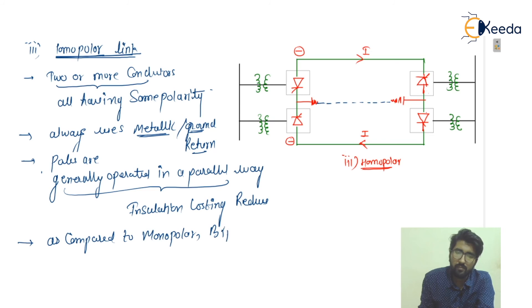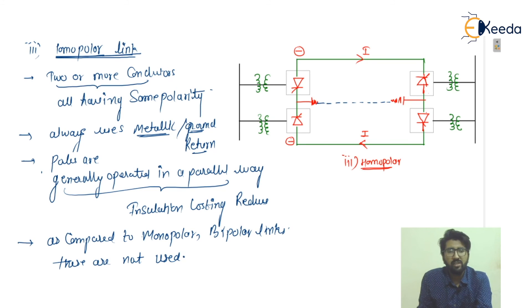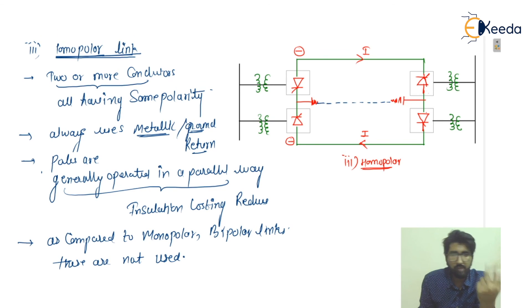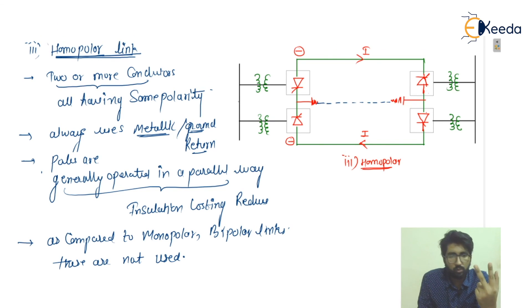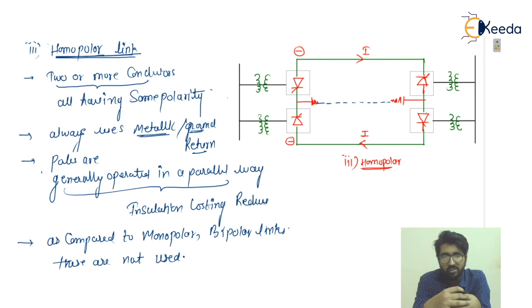Homopolar links are not generally used. The widely accepted links are monopolar and bipolar. To summarize: in monopolar links there is one conductor with ground return; in bipolar links there are two conductors with no ground return; in homopolar links there are two conductors with the same polarity and a ground return. Negative conductors are chosen in all cases due to their low corona effect.